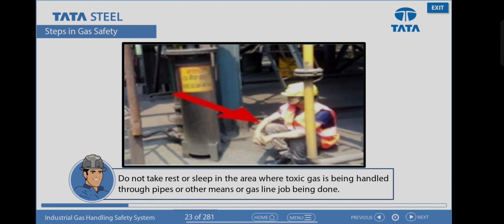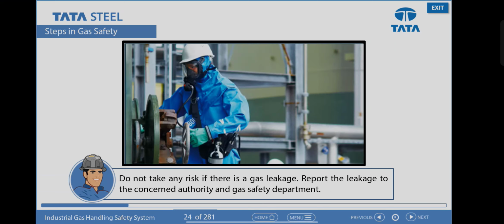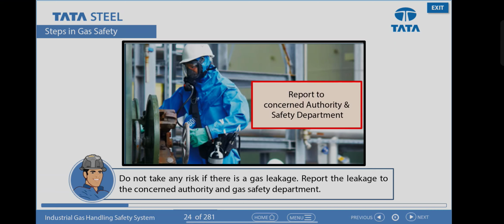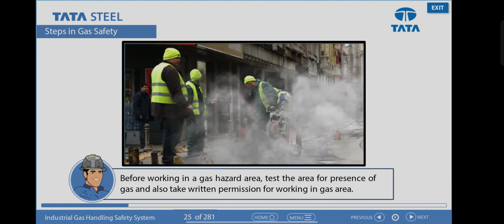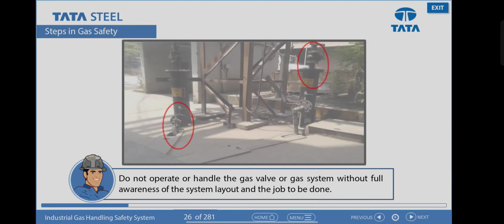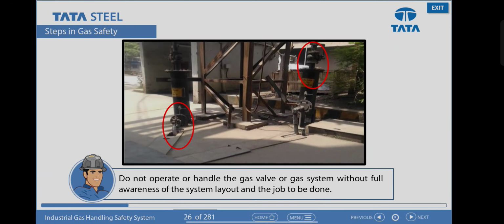Do not take rest or sleep in the area where a gas is being handled through pipes or other means or gas line job being done. Do not take risk if there is gas leakage. Report the leakage to concerned authority and gas safety department. Before working in gas hazard area, test the area for presence of gas and also take written permission for working in gas area. Do not operate or handle the gas valve or gas system without full awareness of the system layout and the job to be done.